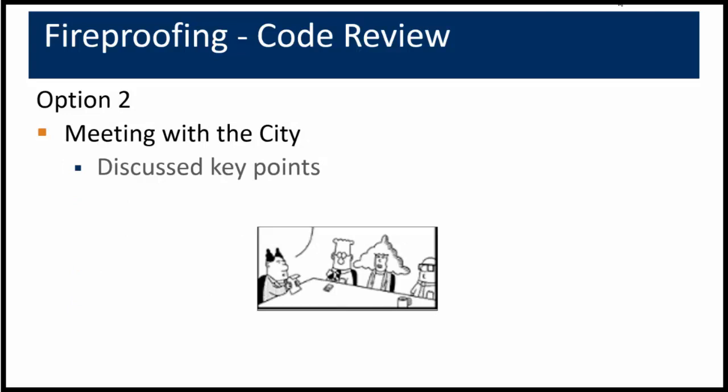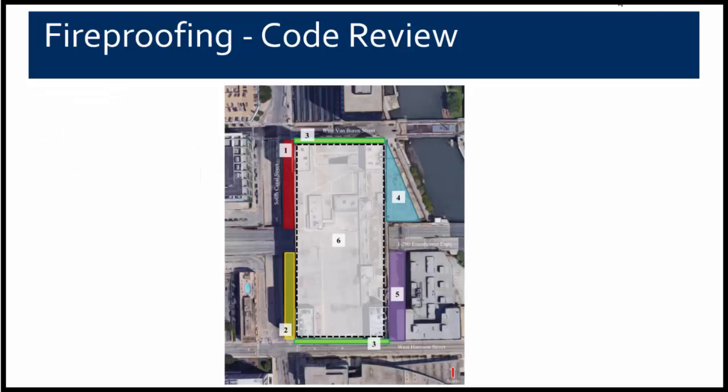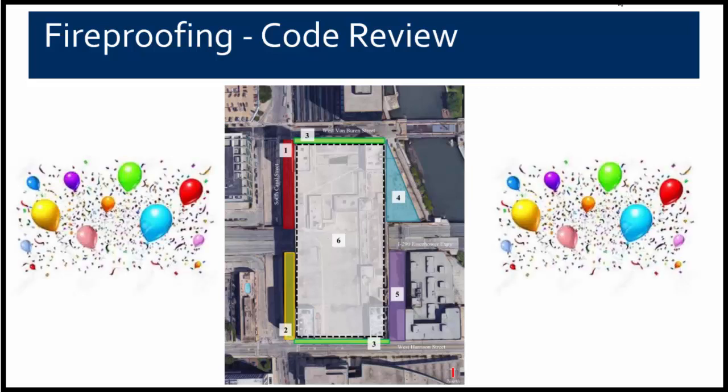Precedent can be a useful point when working with the city or jurisdiction. The Chicago Department of Transportation also prefers to have steel exposed on bridges for inspection — when encased in fireproofing, one cannot inspect the structural integrity of the steel. The final step was presenting the code discussion to the city. In the end, the city agreed that primarily because the areas were outside the building envelope and not supporting building structure, fireproofing would not be required. The end result was that the design team and project owner were happy because millions of dollars in estimated costs are able to be saved.